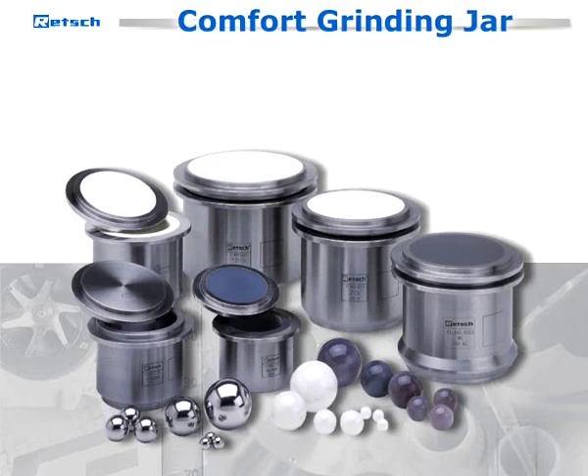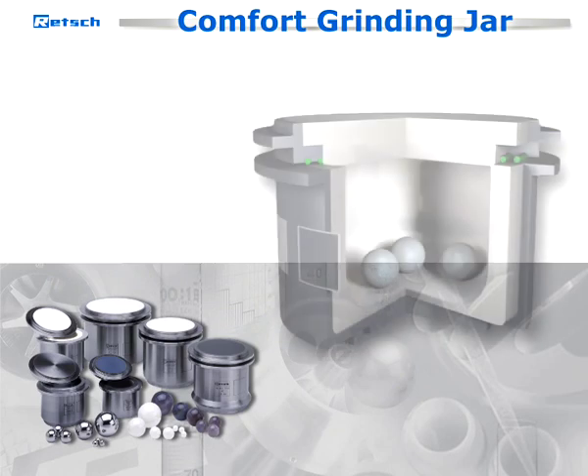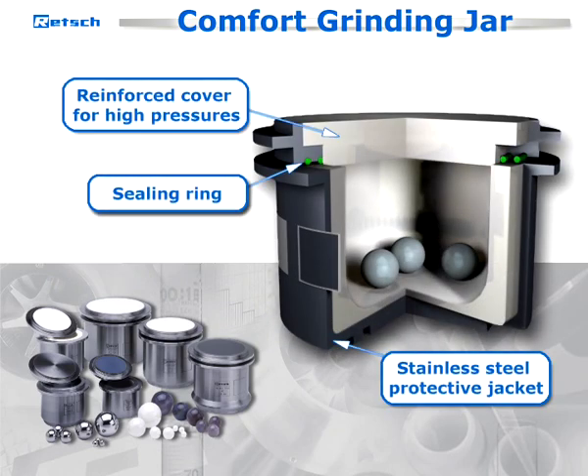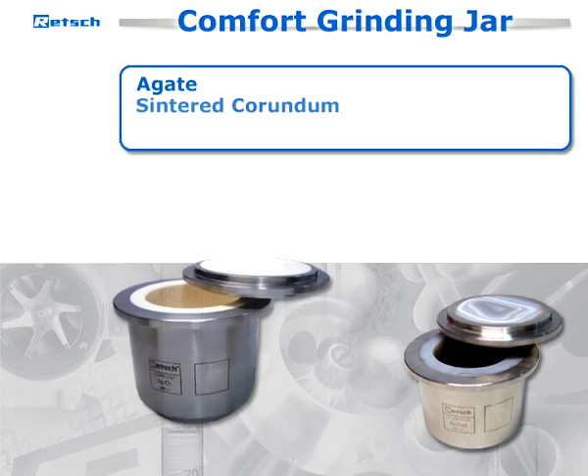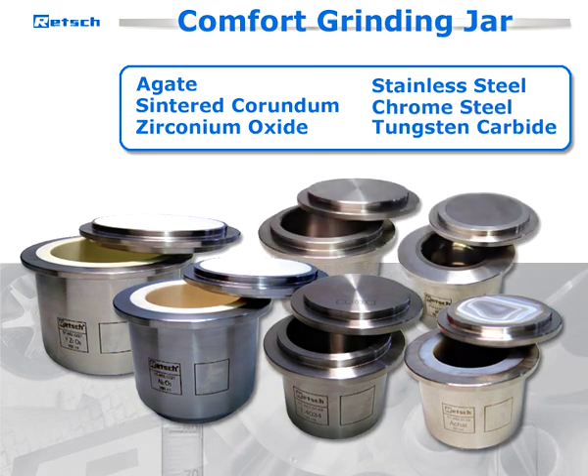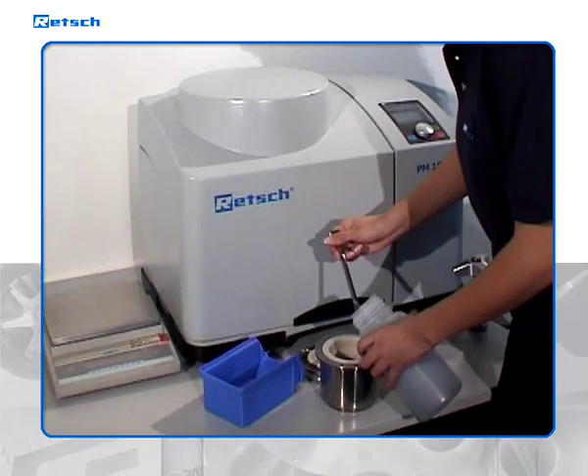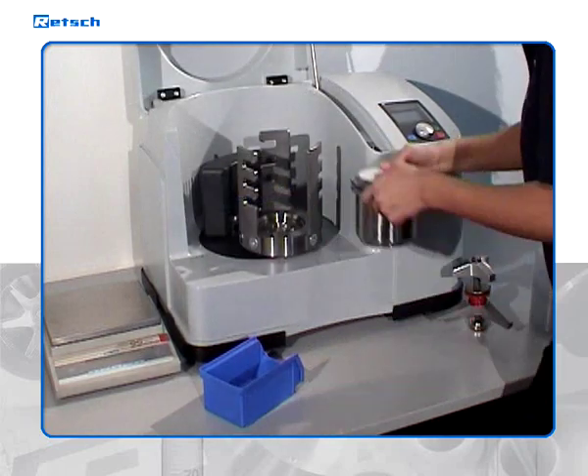The comfort grinding jars are available in sizes from 12 to 500 milliliters. To assure contamination-free results, the comfort grinding jars and balls can be selected from six different types of various steels and ceramics: agate, sintered corundum, zirconium oxide, stainless steel, chrome steel, and tungsten carbide. The selection of jars and balls depends on both the sample volume as well as the grind fineness to be achieved and the degree of purity required for subsequent analysis.